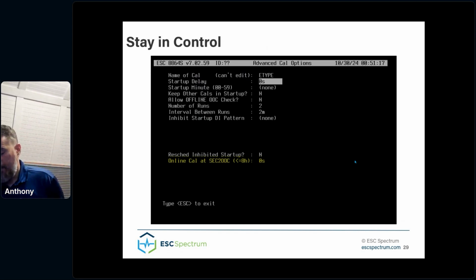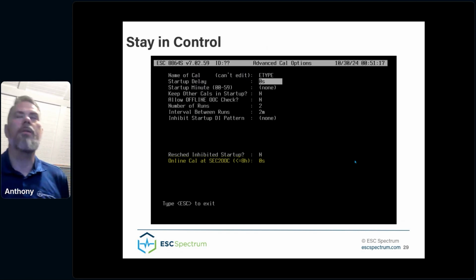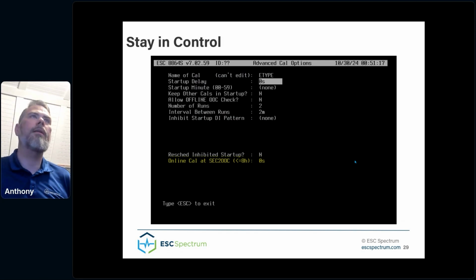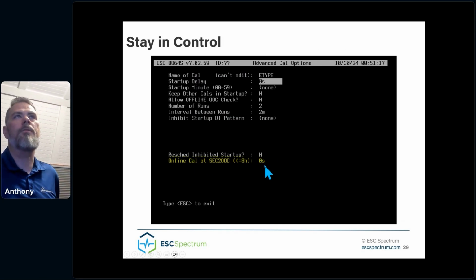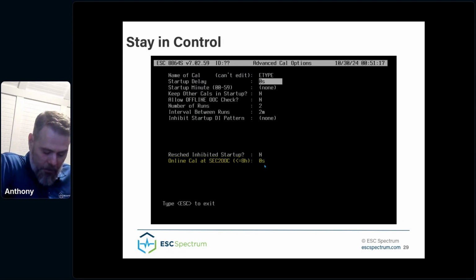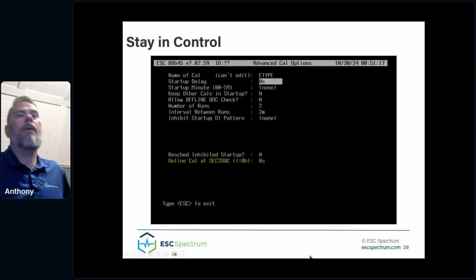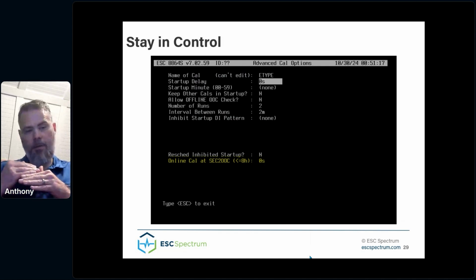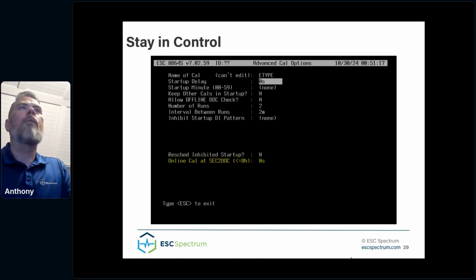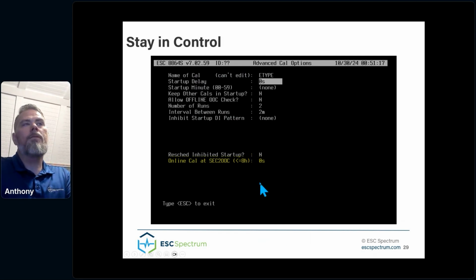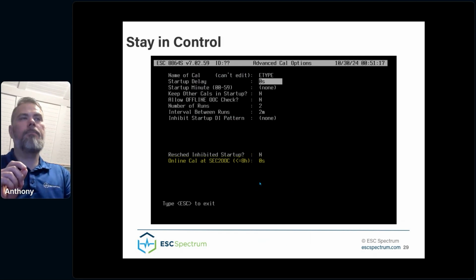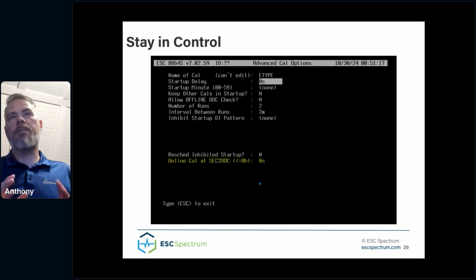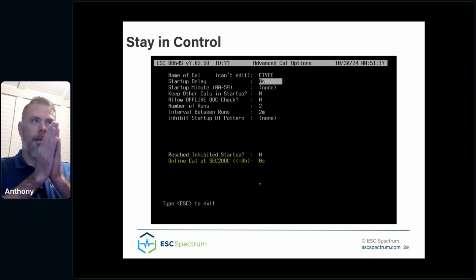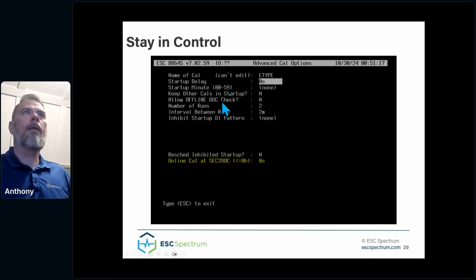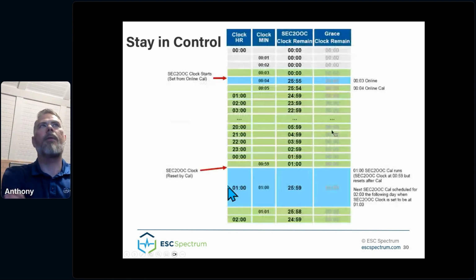Okay, another setting we added to calibrations was a way to help stay in control using the math SEC2OOC functions. There's a setting now called online cal at SEC2OOC less than or equal to 8 hours. Now we set it at less than or equal to 8 hours just to avoid the complexities that come along with a grace period, because as soon as you enter your grace period, you typically, SEC2OOC will immediately get another 8-hour jump. So what this will do is the calibration that this setting is configured at will run if any data channel has a math function SEC2OOC value less than the configured threshold set here, and the channel is online. And again, we've provided some examples in the manual.